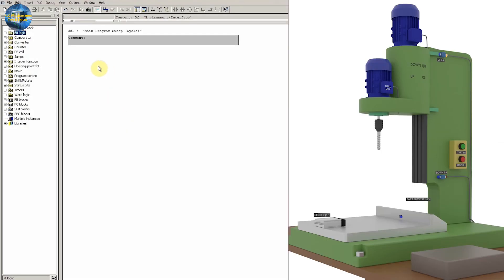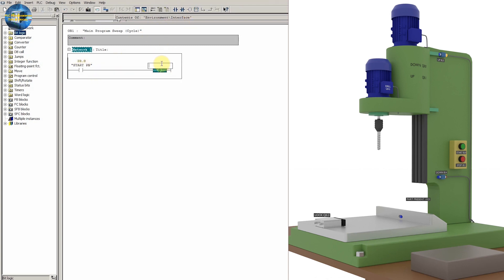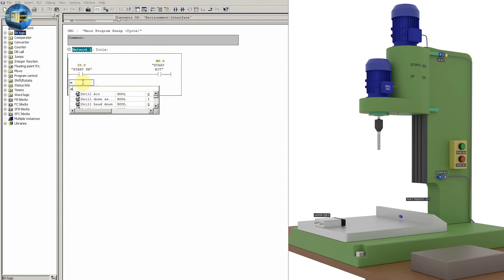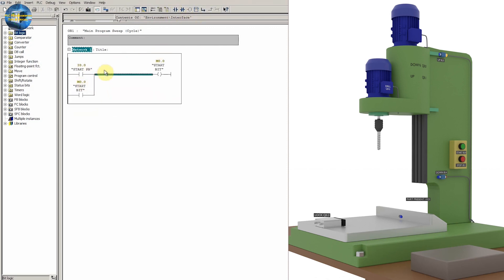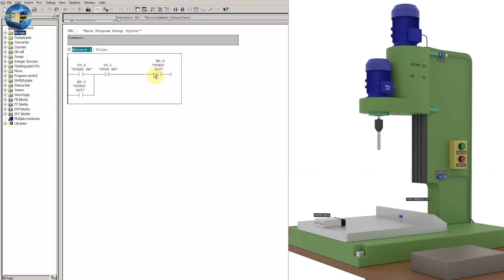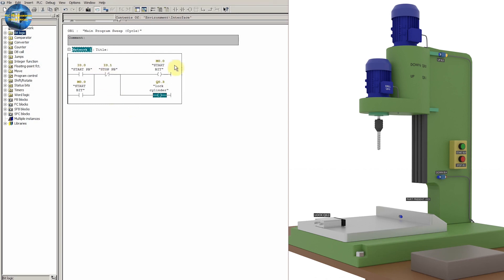In network one, we will make a simple hold-on logic using start push button I0.0 to hold on the start bit M0.0. We can put a normally closed contact of the stop push button I0.1 to turn off the start bit M0.0. We can also turn on the output coil Q0.3 lock cylinder along with the start bit.